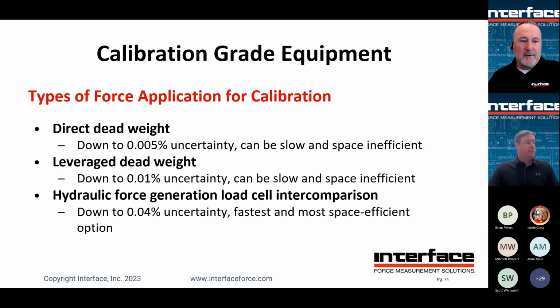So here are some different ways to apply force. Direct dead weight: this would be a dead weight machine dedicated to applying dead weights, automated. It's a very large machine, not very space efficient. It's a very slow type of calibration, but it typically yields the best, lowest uncertainty levels of any of the types of calibrations that we're going to talk about.